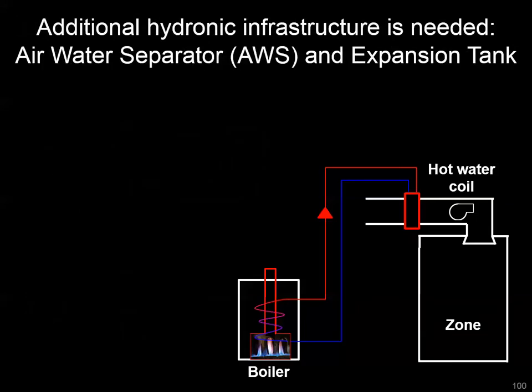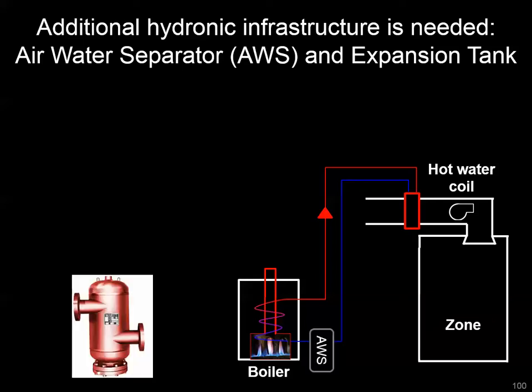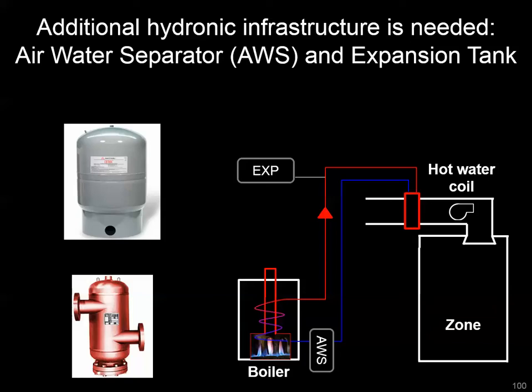There's some specific infrastructure needed in a hot water system. We have an air-water separator near the boiler that extracts entrained air from the hot water system — it's also the makeup point for water. Then there's an expansion tank, a device with an air bladder inside, meant to take up the extra volume when water heats up. Water is incompressible but changes density at different temperatures, so as it heats from startup up to around 180 or 200 degrees, it expands, and the expansion tank accommodates that additional volume.